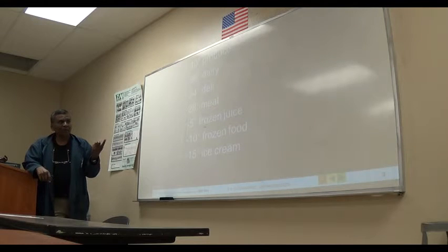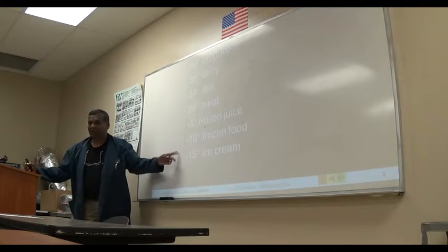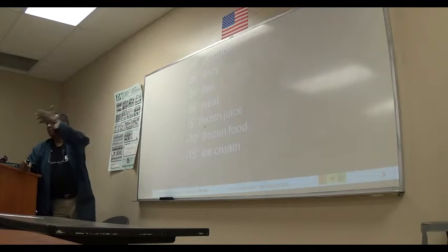And what about 408 or 409? That's a low temperature one too, isn't it? 409 is a replacement for R12. 408 is for 502, which is low temperature, but 408 is an HCFC. This one is pure HFC. So are they doing away with the 408? No, not yet. Nobody has mandated anything about the 408 or 409. They were both drop-in replacements, 409 for R12 and 408 for 502, but they're HCFCs.